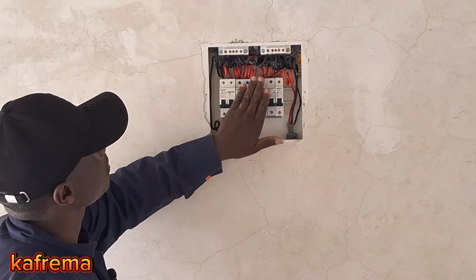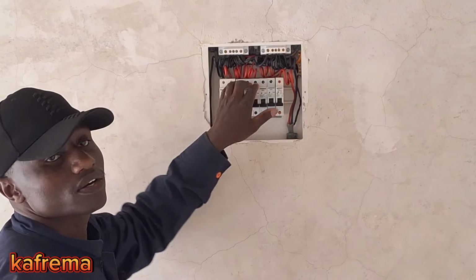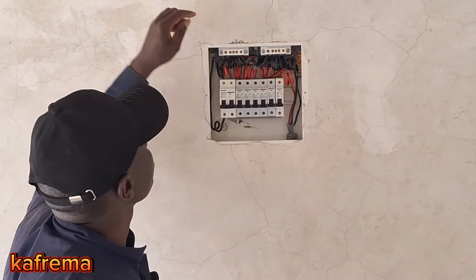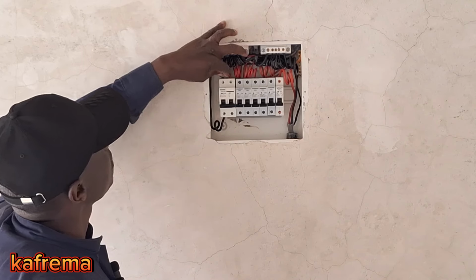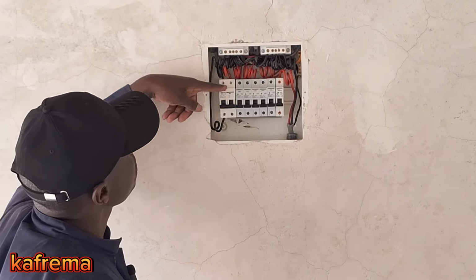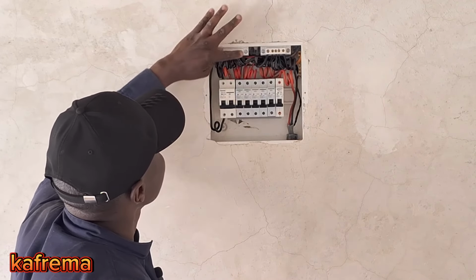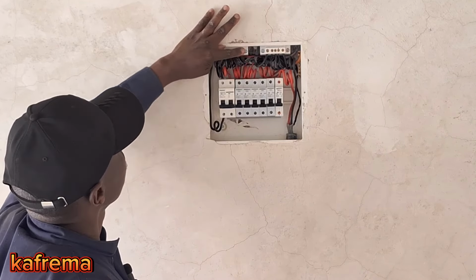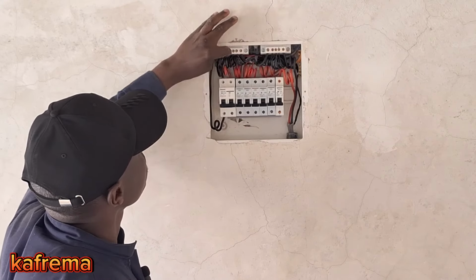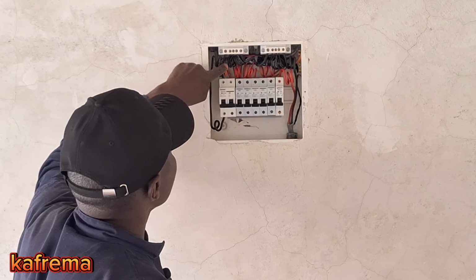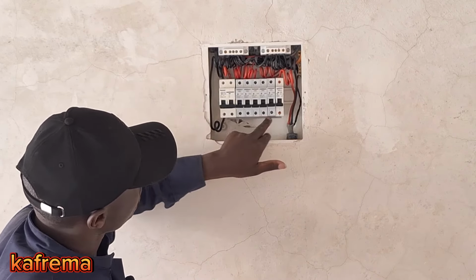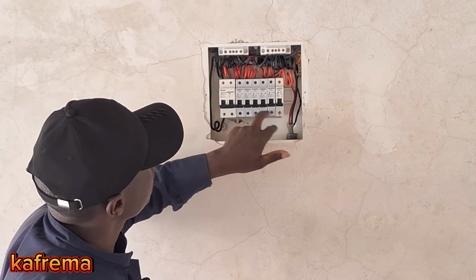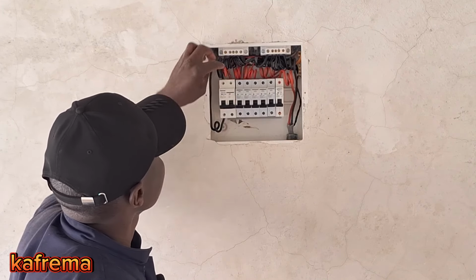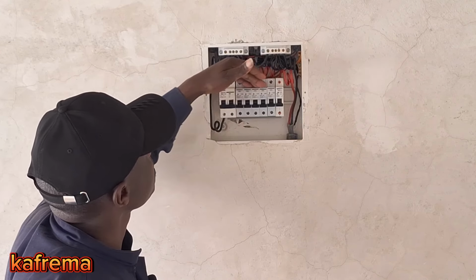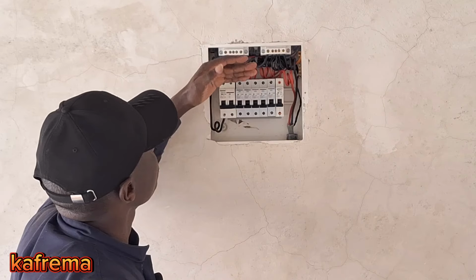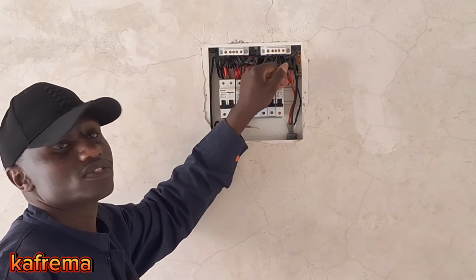So now our circuit, our 6-way consumer unit, is completely wired. From the source through these 2 cables here, we get to the main isolator. The main isolator's neutral we take back to the neutral bar to give all the necessary circuit breakers neutral connection. The line is connected through this bar down here to all the circuit breakers. Then we have 6 circuit breakers, with ratings according to where each is going to serve.